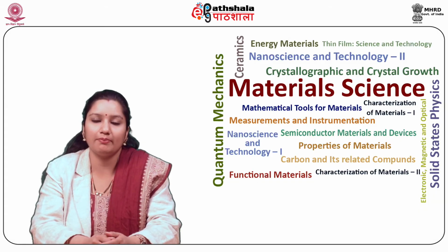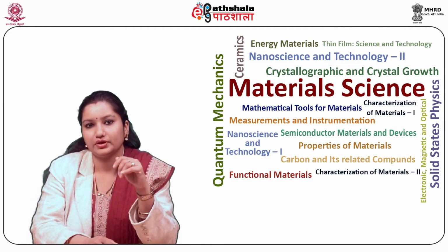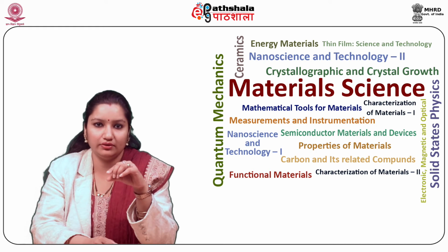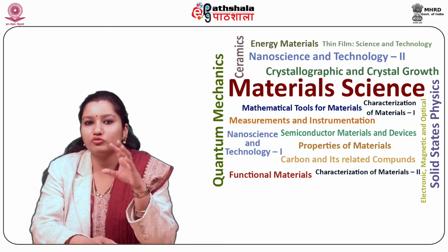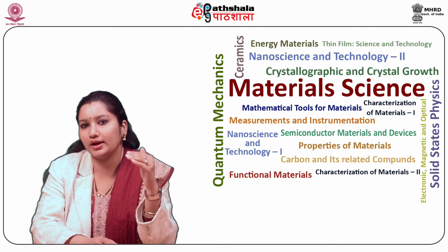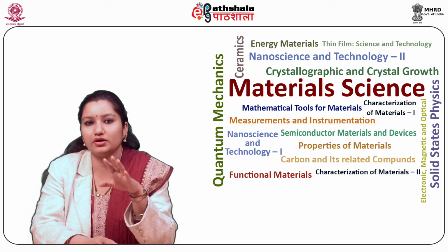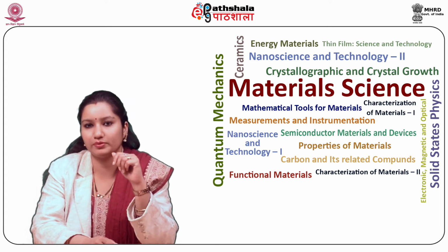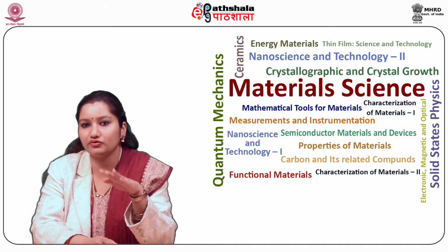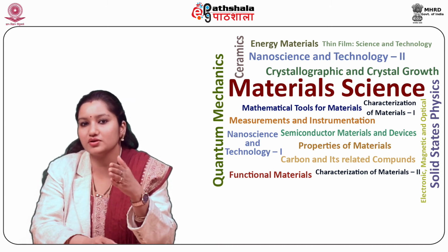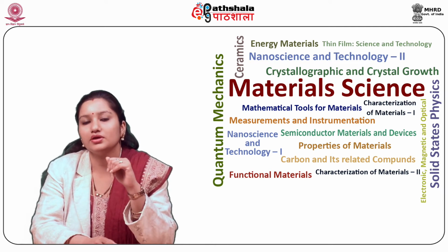Now let us study the sample preparation for the TEM analysis. The TEM sample should be thin due to the absorption of the electron in the material, so special care must be taken while cutting a thin slice of the metal so that the specimen is not deformed during its preparation. This is because plastic deformation can introduce unwanted structural defects in the microstructure that are visible in TEM images.